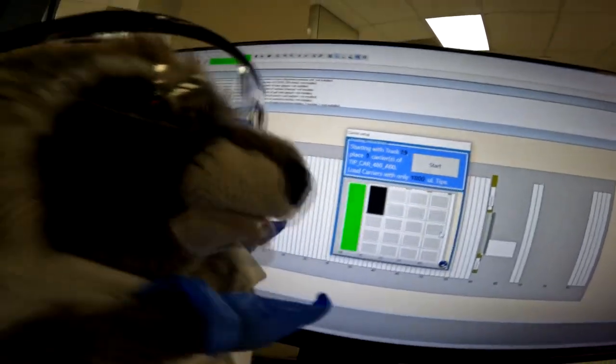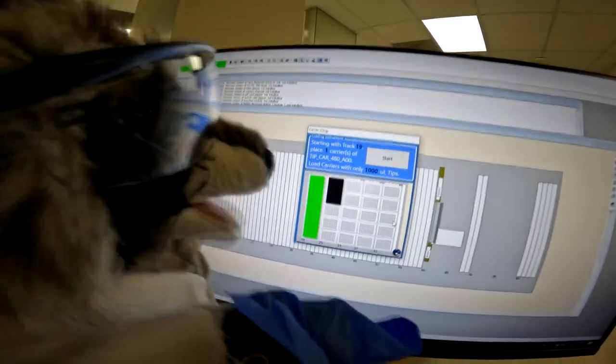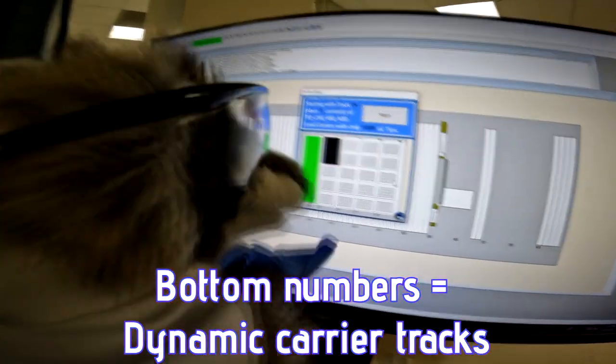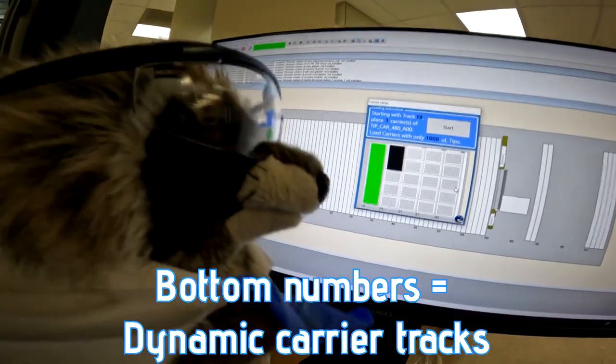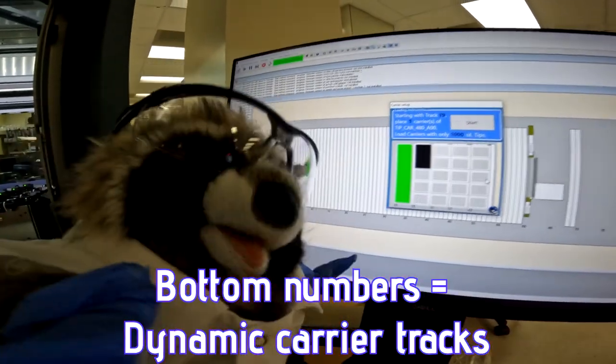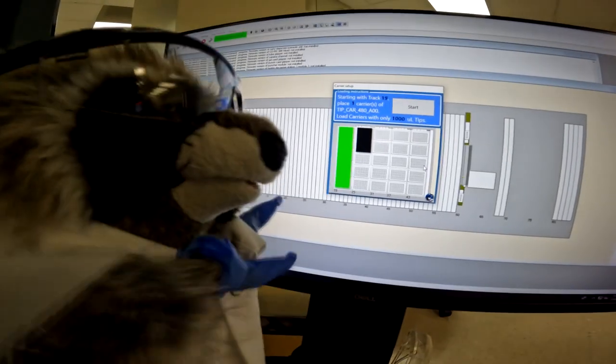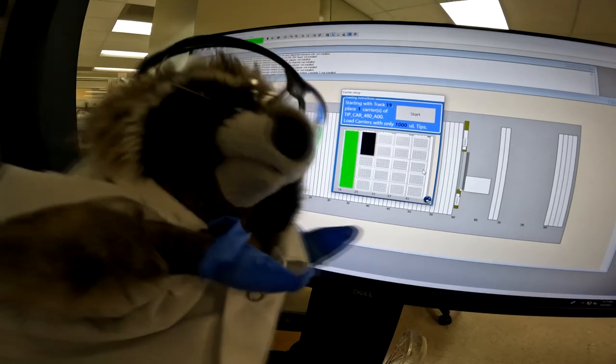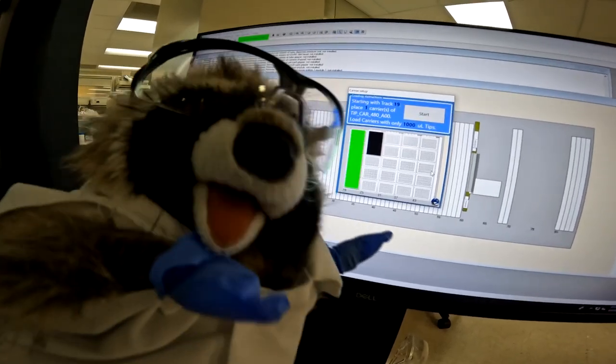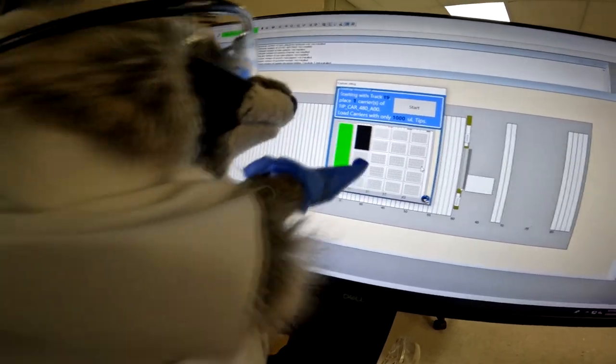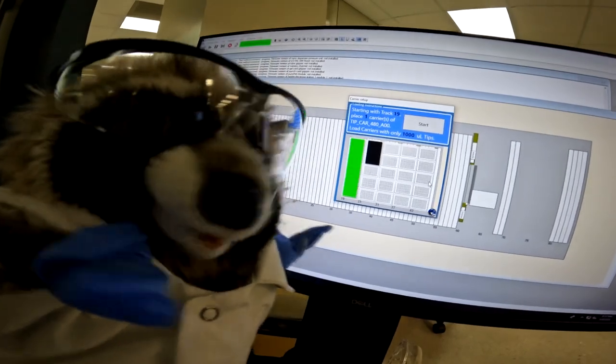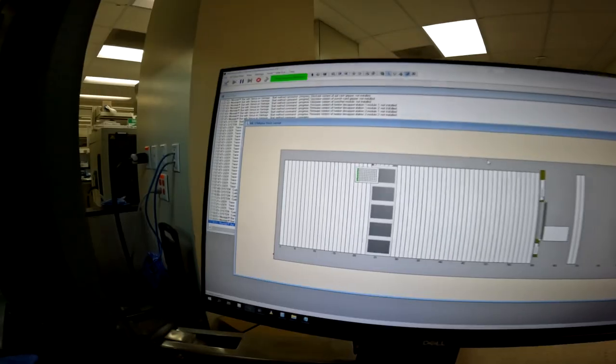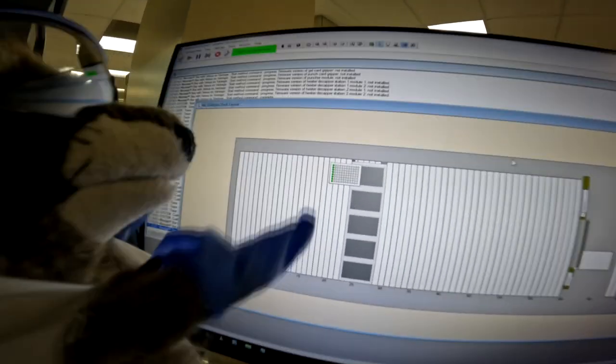So it tells you which track to start with, place one carrier there, and oh look, those numbers change in increments by six because that's the width of the track. Flashing which one you should load, and that black box - if we had to load two or more carriers, we would skip those positions. Only 1,000 tips, let's do it.